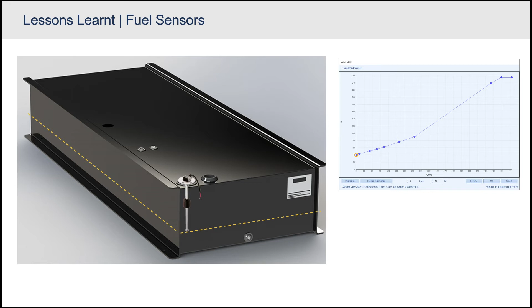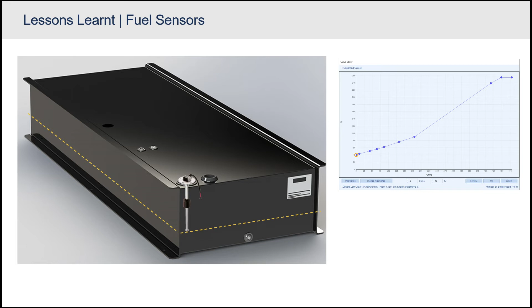What we've done for this one, on the right, you'll see the configuration on the controller. It allows you to stipulate certain points, and with that you can recalibrate that sensor so that you actually get true information in. You'll see those blue dots. Those blue dots are specific measuring points that we've got. We knew when it is 100%, we know when it's 60%, 40%, and so forth. And you'll see it actually hits the bottom at 40%, which helps it to be very accurate. The problem is that as soon as it reaches 40%, you don't know what's happening from there to 0, because that sensor can only show you up to 40% and nothing below that. So you must understand what you're seeing, and then you can start trusting your instruments and make proper use of them. Okay, so that's from a fueling point of view. So let's carry on.